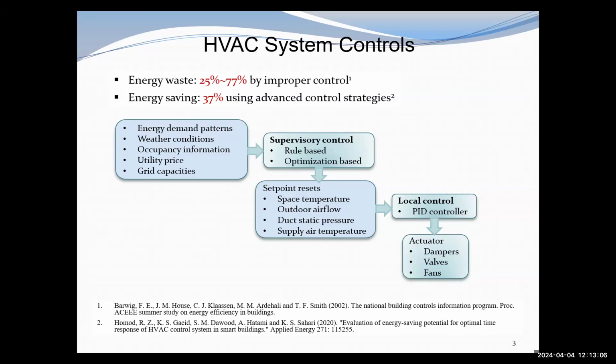And the local controls are designed as single loop feedback control with the PID controller in this control loop. The actuator will be adjusted to achieve the desired set point. To maximize the energy saving potential, the local control loops are supposed to be stable and also have a very fast and smooth response to the dynamic set point resets. However, due to improper control strategies, 25% to 77% of the energy can be wasted. And if we can adopt advanced control strategies, up to 37% of the energy can be saved.